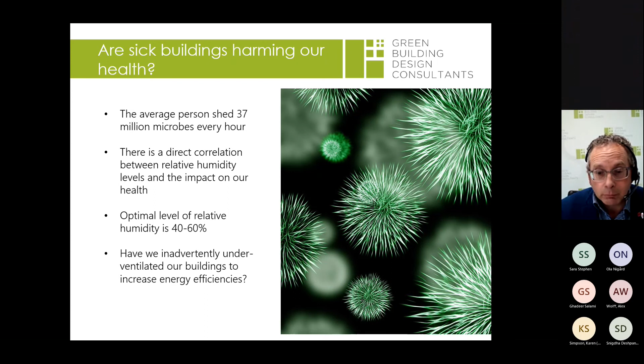Our institute, the CIBSE guidance, has for a long time talked about the need for humidity control in sensitive areas, typically requesting it to be 50% plus or minus 5%. I think that really came around in the 80s, when we started introducing computers into offices, and people experienced issues with static electricity compared to the old mechanical typewriters. So there was a push to say, to avoid static electricity, humidity should ideally be kept between 45 and 55.